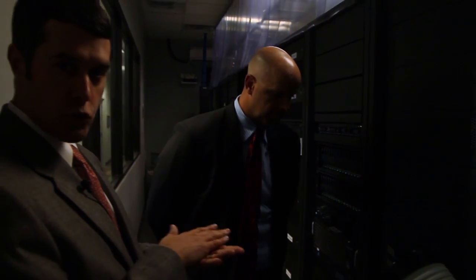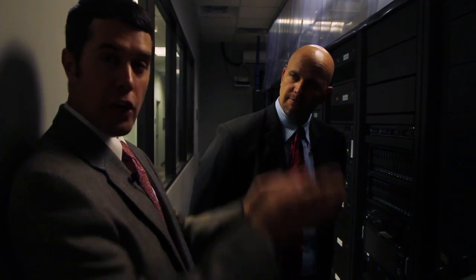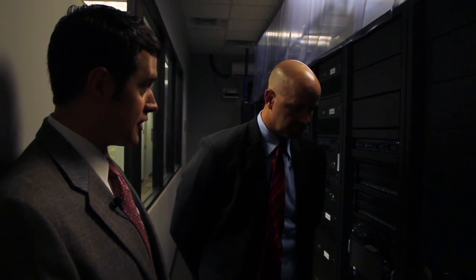But then you always have to ask yourself, what happens if that interrupts, or if it just outright fails? And so in this case, the one you're looking at, we do have uninterruptible power supplies, or UPSs, right? And what these things do is a handful of things. First, it will measure the power coming in. If it's too high or too low, it will regulate that for you and give your equipment some sort of normalized power. The other thing it'll do is if there's a brownout condition or a failure for a moment in time, it will stabilize the load being given to the equipment in the rack. And so that's important for the consistency, but we also know how ugly things can be if surges or something like that happens to very sensitive technical equipment.